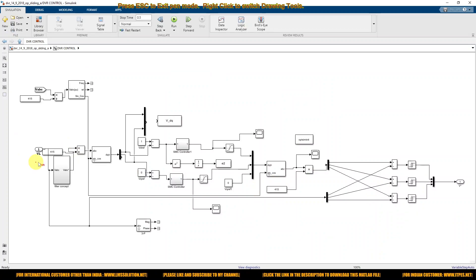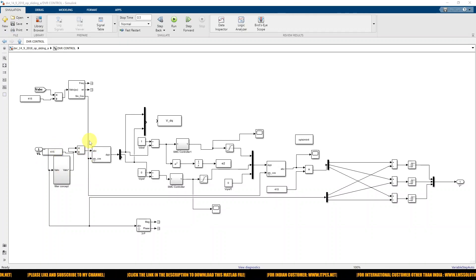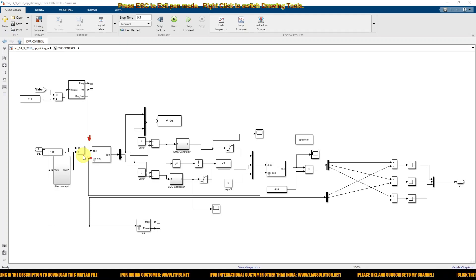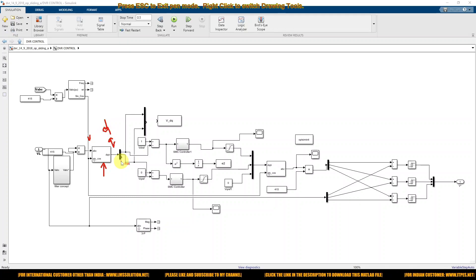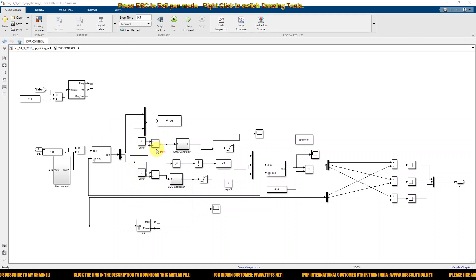Inside the DVR control, we first convert the load voltage into per unit by measuring it, filtering it, and dividing by 415. Since we have ABC quantities, we convert them to DQ0 using an ABC-to-DQ0 conversion block so we can control the system more easily. We then take only the VD and VQ voltages — VD is compared with the reference voltage and VQ is compared with zero.